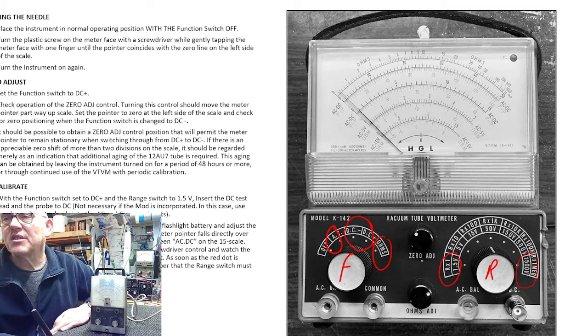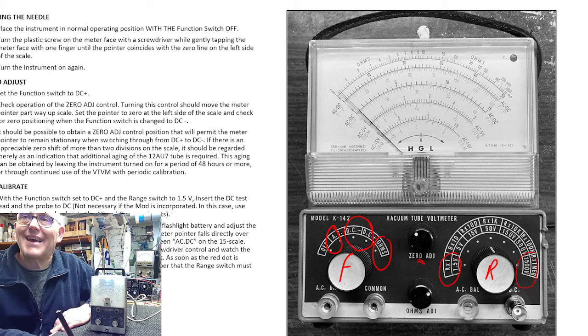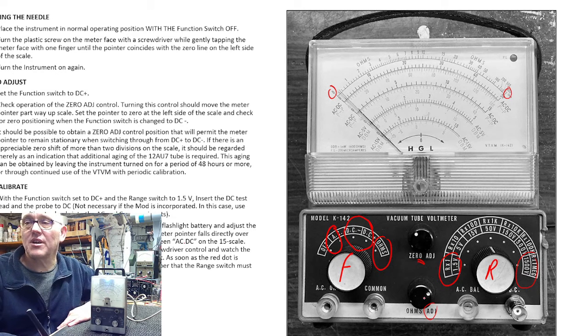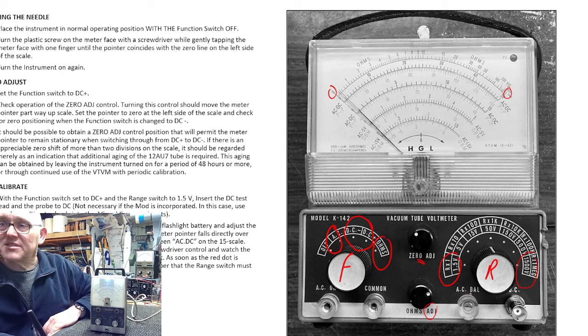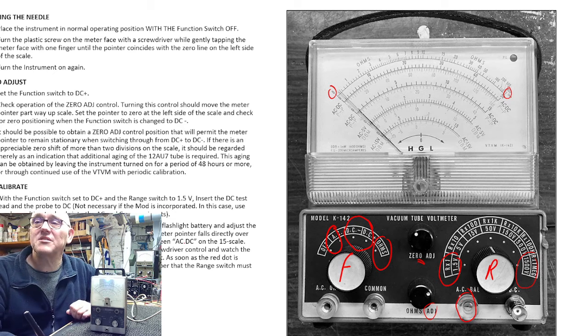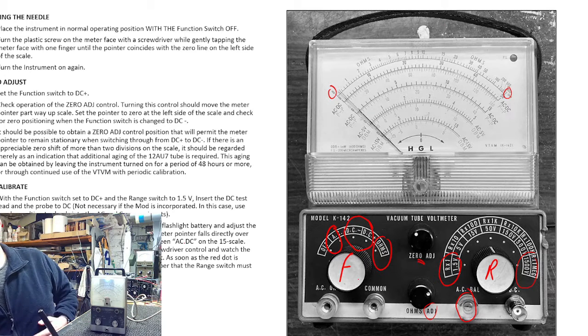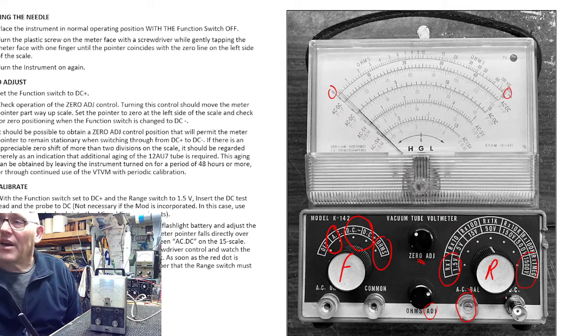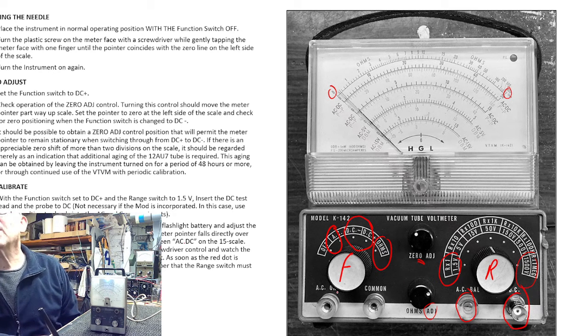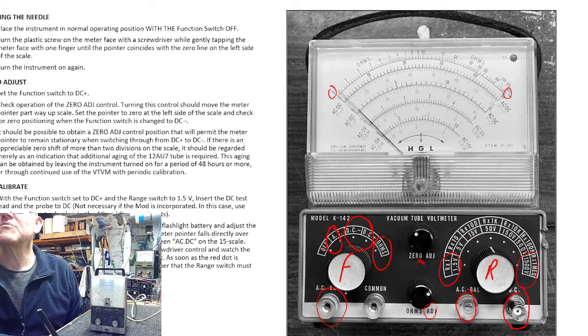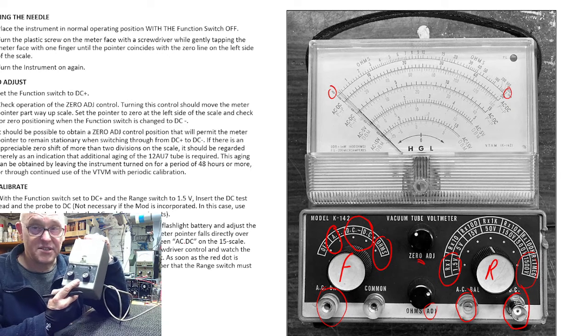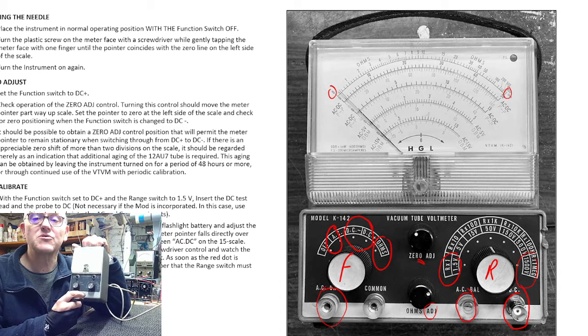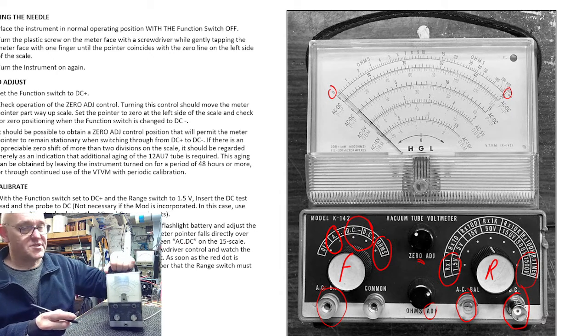The other thing you find on the input is a zero adjust, and that is to set the meter at 0 with no input. We have an ohms adjust, which is to set the needle at the infinity mark, with no resistance load connected during the ohms measurement. And then we also have an AC balance pot. Now some meters the AC balance pot is in the back, some it's in the front. Just depends on the make. Other thing you can see on this one over here, sorry I'm having to lean over, is you have a separate DC input compared to the AC and ohms input. Now on this meter it only has a single input, where AC, DC and ohms is all measured at the same point. We'll see that in a minute as well.